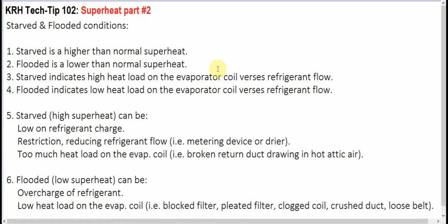You don't know at that point whether you have a low load condition or a high load condition on the evaporator coil. You also don't know whether you have an overcharge, low on Freon, or a restriction issue. So what you're doing by checking superheat is verifying if you have a flooded condition or a starved condition. If my superheat's high, I'm starved. Superheat's low, flooded. This then leads you in a direction to determine why that condition exists and what the best means are to remedy that problem.